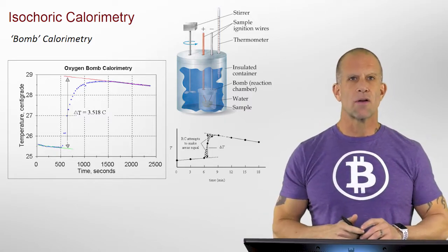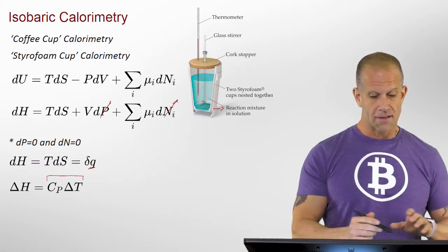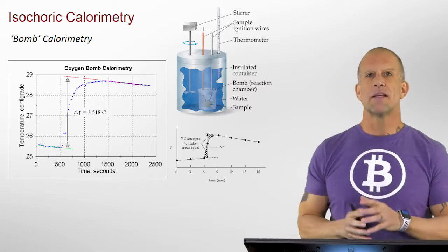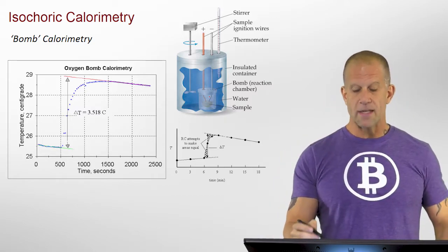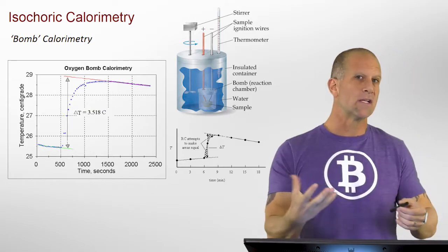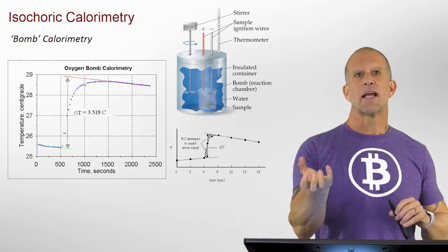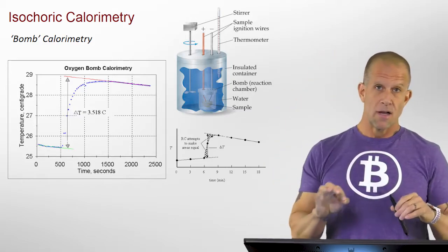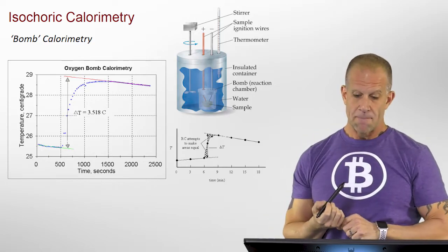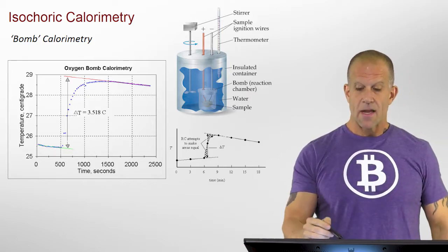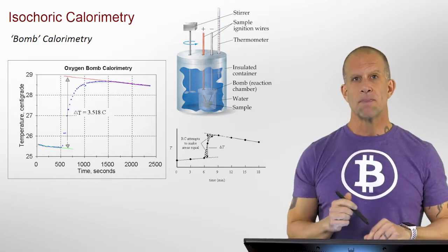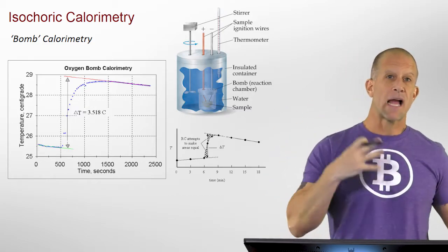Moving on, instead of constant pressure you can work under constant volume. Under constant volume, the work term goes away and you look directly at the internal energy of the system. This is called bomb calorimetry because you're loading something — most commonly with an oxygen bomb — so you're looking directly at combustion. This is common in the food and pharmaceutical industries. You put a sample in, load oxygen at high pressure under constant volume conditions, then ignite it to hopefully completely combust the sample. You can do this with a known material to get the heat capacity of the whole system.